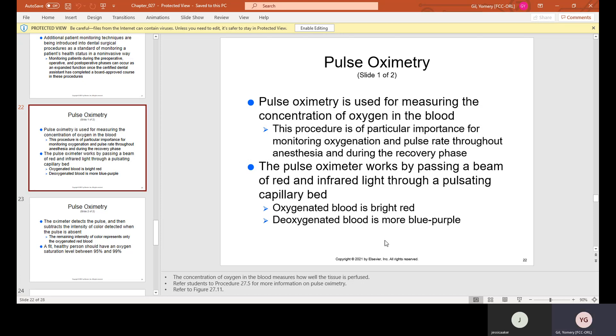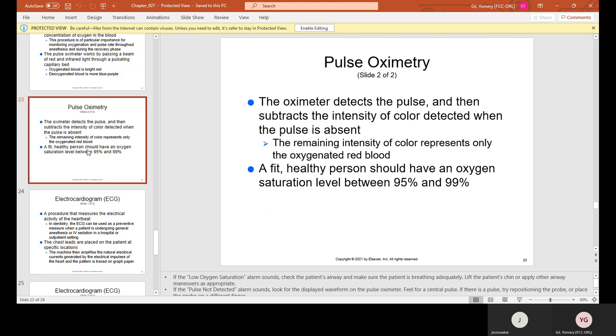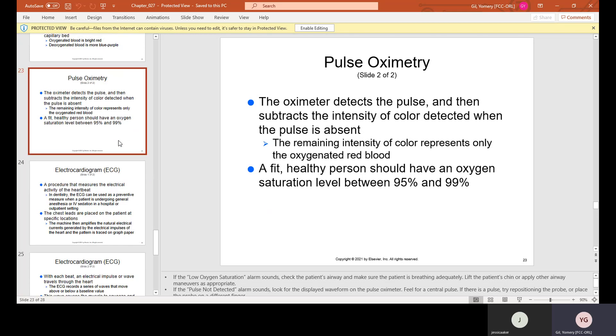Pulse oximetry is used for measuring the concentration of oxygen in the blood. This procedure is of particular importance for monitoring oxygenation and pulse rate throughout anesthesia and during the recovery phase. The pulse oximeter works by passing a beam of red and infrared light through a pulsating capillary bed. Oxygenated blood is bright red and deoxygenated blood is more blue-purple. The oximeter detects the pulse and subtracts the intensity of color when the pulse is absent, leaving only oxygenated red blood. A fit, healthy person should have an oxygen saturation level between 95% and 99%.